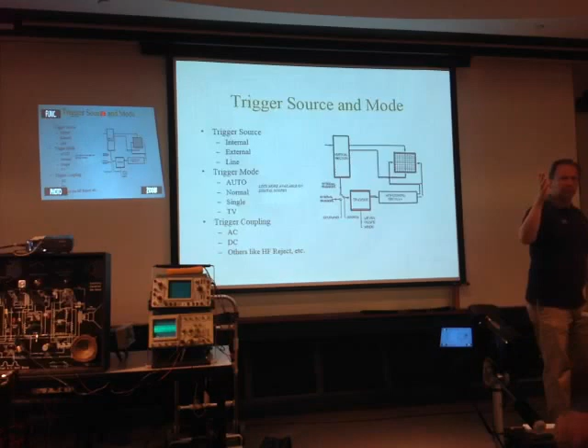Line triggering, who knows what line triggering is? 60 cycle. Triggering on the 60 cycle line input, exactly. Now where would that be useful? You want to look to see if there's any particular aspect of your signal that is synchronous to your ripple and your power supply. Okay, or something else going on at the 60 hertz line. So that way, it's a real simple thing. If I know I'm looking at ripple, or maybe I'm looking at an IF signal, and there's a little bit of ripple on the B+. So if I look at it, it's kind of moving all around back and forth. If I go to line triggering, I might get just a slanted portion of where I'm looking at a portion of the ripple, but it's stable. Because I'm always looking at the same portion of that because it's synchronous to the line.